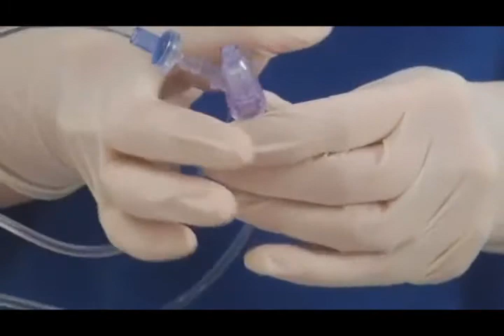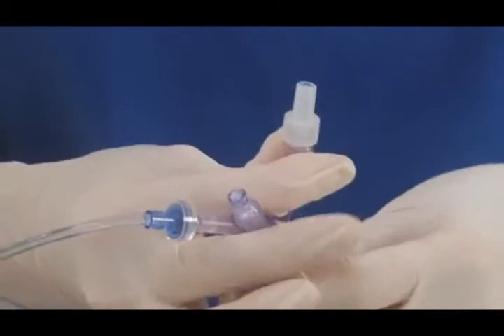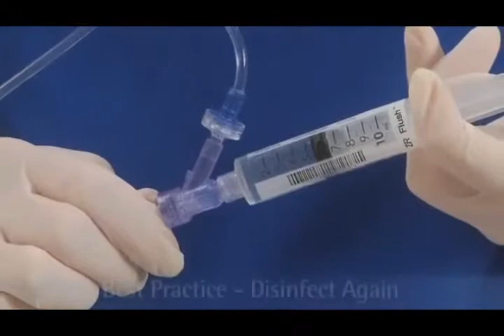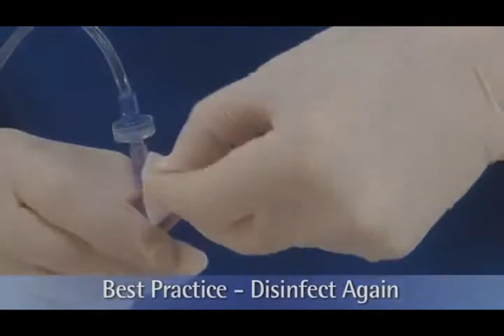After disconnecting the secondary administration set, the clinician follows best practice by placing a new sterile dead-end cap on the end of the secondary tubing set. The clinician then disinfects the access top of the Caresite integrated Y-site with alcohol, allows it to dry, and flushes the Y-site according to healthcare facility protocol. Best practice is followed by disinfecting the access top of the Caresite Y-site again.